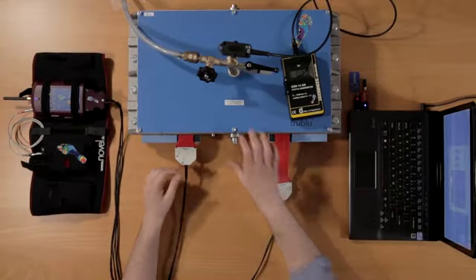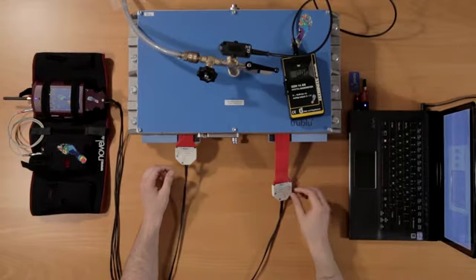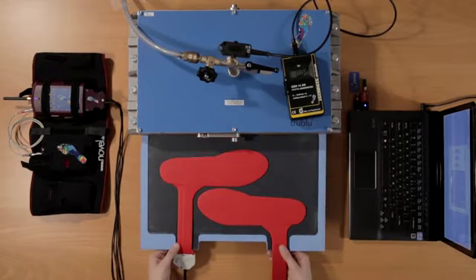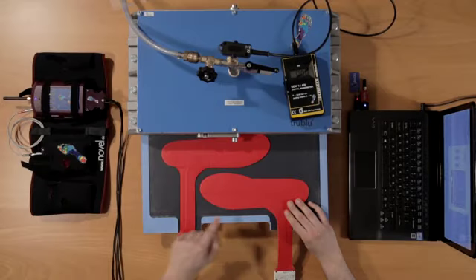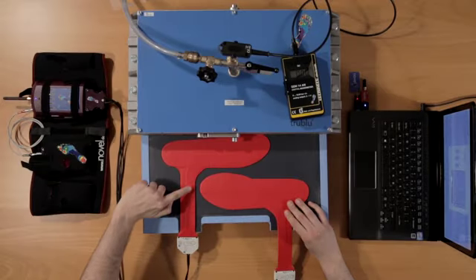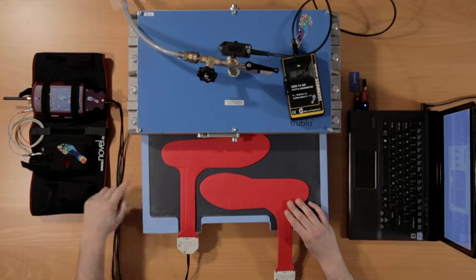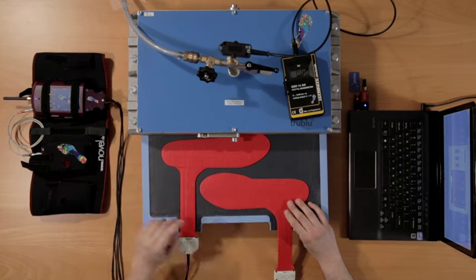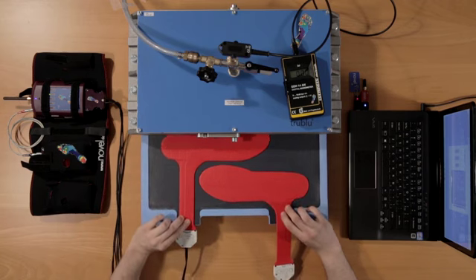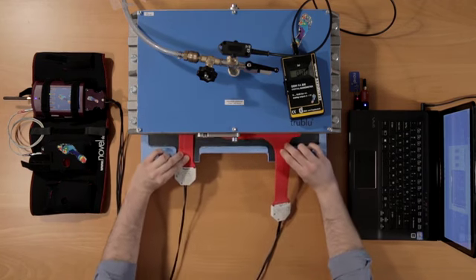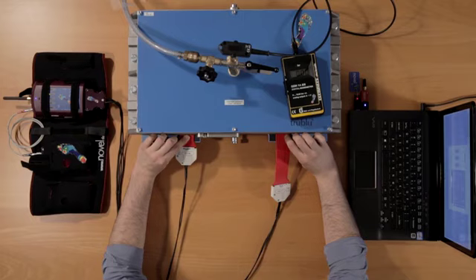Step 4. Open the calibration device by opening the latch and pulling out the calibration board. Place the insoles in an arrangement with the insole serial number up where they are not touching each other and are at least 1 centimeter away from any of the edges and the other insole. Close the calibration board while holding the insole leads in place so they do not shift during movement.